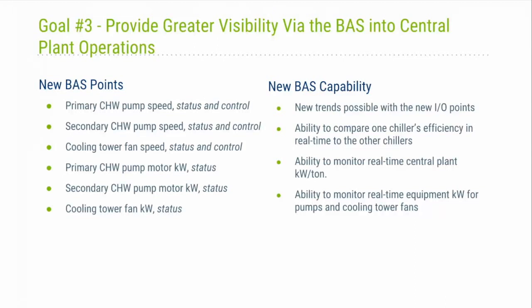So here we're showing all the new points, status and or control for chill water pumps and pump motors, cooling tower fan speed, and fan KW. And then some of our new capabilities, we could run new trends with the new input-output points. We had the ability to compare one chiller's efficiency in real time to the others. Also, the ability to monitor in real time the central plant KW per ton. And we could monitor real-time equipment KW for pumps and cooling tower fans.